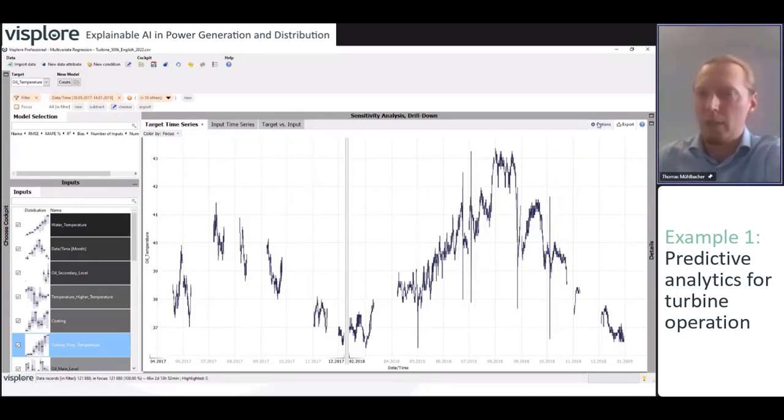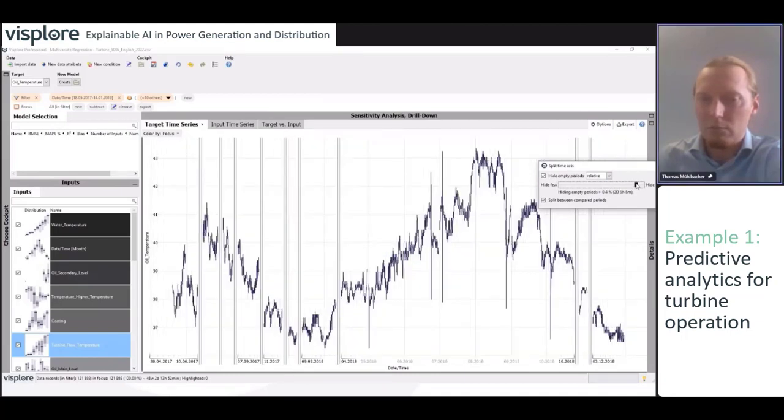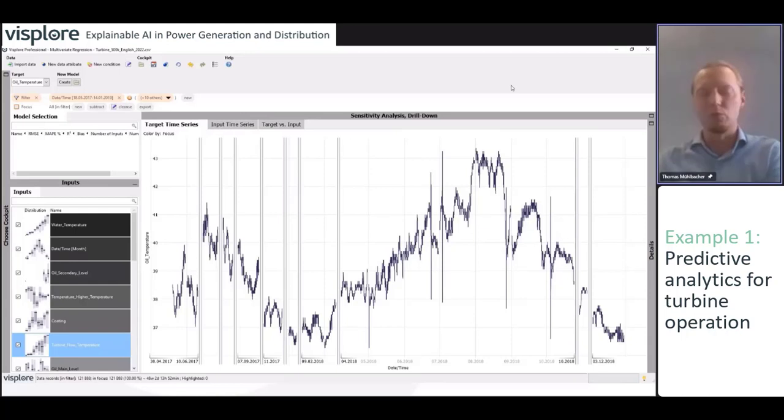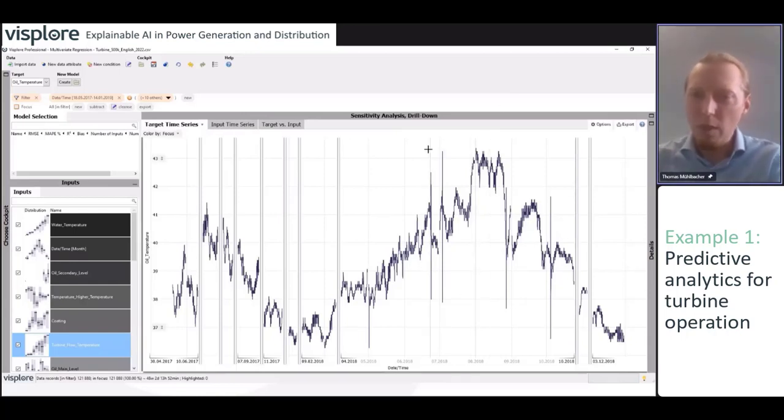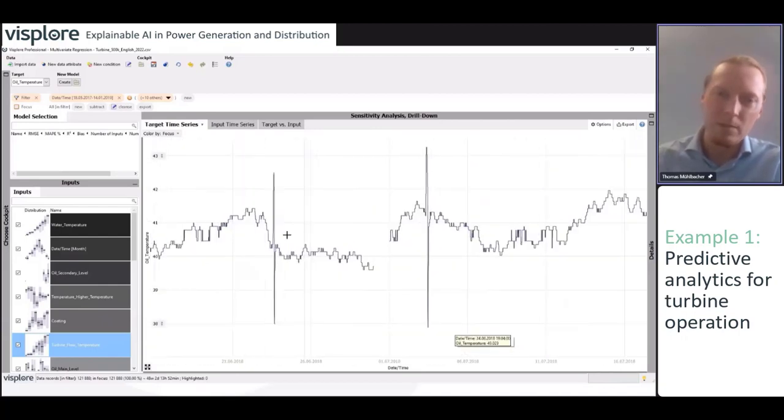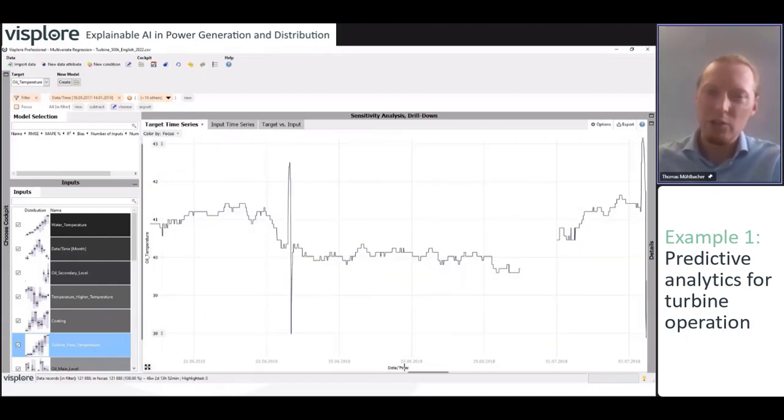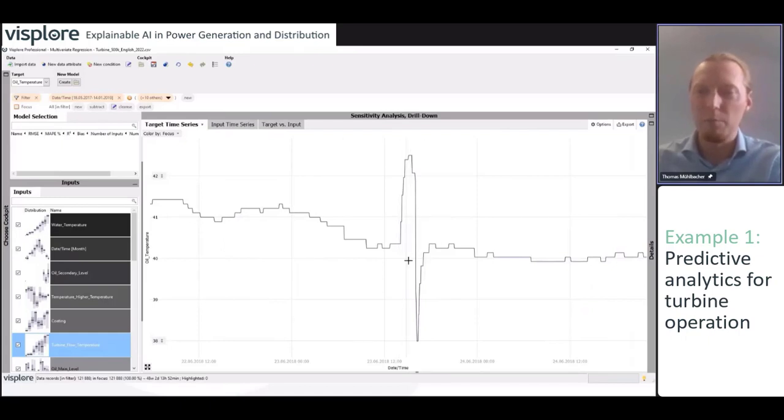This is okay. We can also in this visualization collapse the gaps so that gaps don't take so much space. See, yeah, maybe like this. Now we see a nice time series of data that we can use. We still have one more thing here that's a bit disturbing, and these are these small spikes here. And these are actually interesting because they occur during normal operation, where the oil temperature makes such a pattern. And this could actually be something that we want to detect with our dynamic tolerance thresholds.